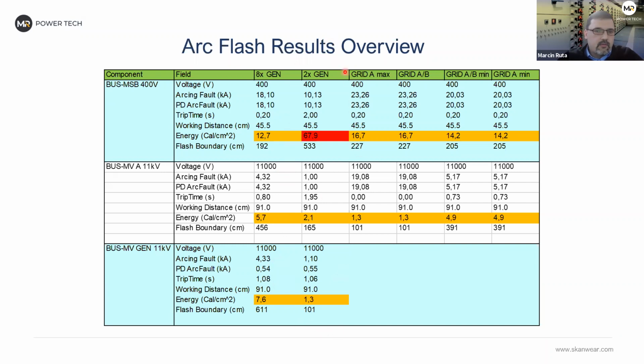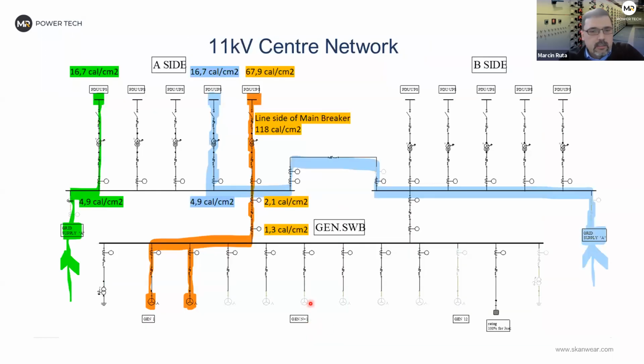And as you can see, in the 2 generator operation mode at the low voltage part, it was quite dangerous. And I will explain in a minute why. But at the same time, what is illogical, you will see that on the 11 kV side, this is actually one of the best scenarios that we can have. So those are not logical results. Just to give you an overview, that was the model for this specific project. We have the 2 supplies, we have generators, multiple generators. And at that time, 2 generators were likely to happen at the beginning of the project.